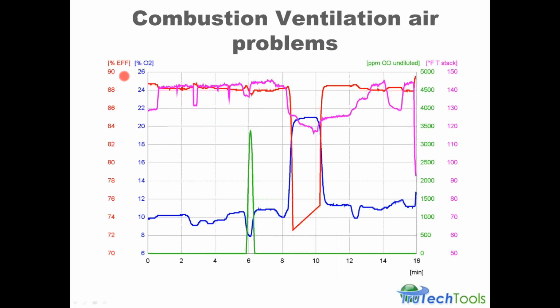The purpose of this slide, and by the way, this was created using a Testo 330 combustion analyzer and software called Easy Heat. Very powerful because it gives you this kind of strip chart recorder output on a real-time basis, and I've used it that way. It's a very, very handy tool to see all the dynamics going on. The basics of this slide were to show that there are a lot of dynamic things going on. When oxygen levels change, efficiency levels change, carbon monoxide levels change, stack temperatures change, all kinds of changes happen at all kinds of times.